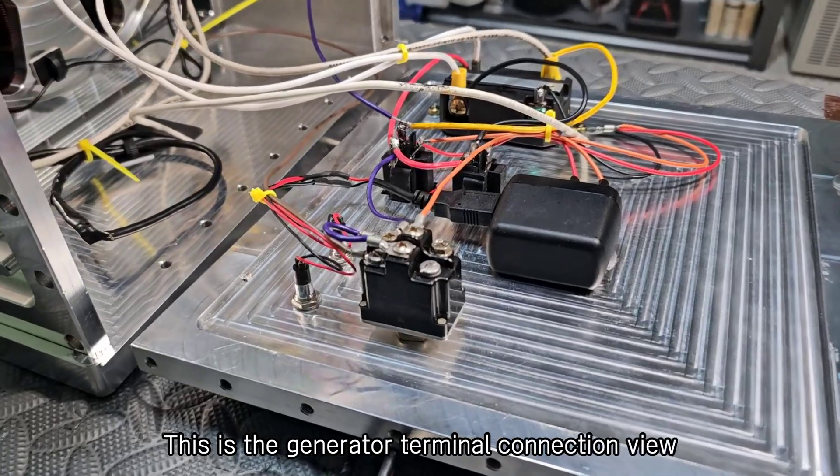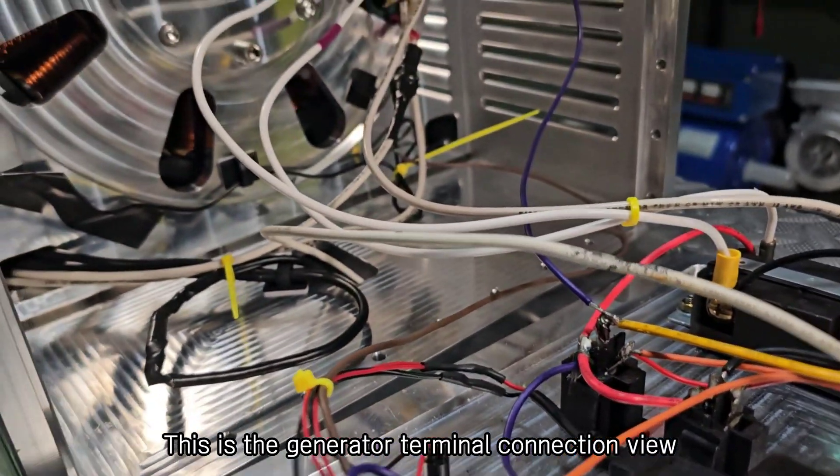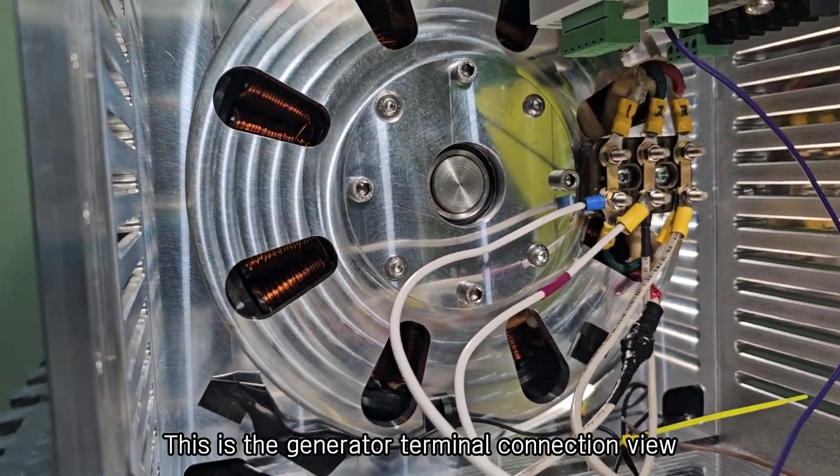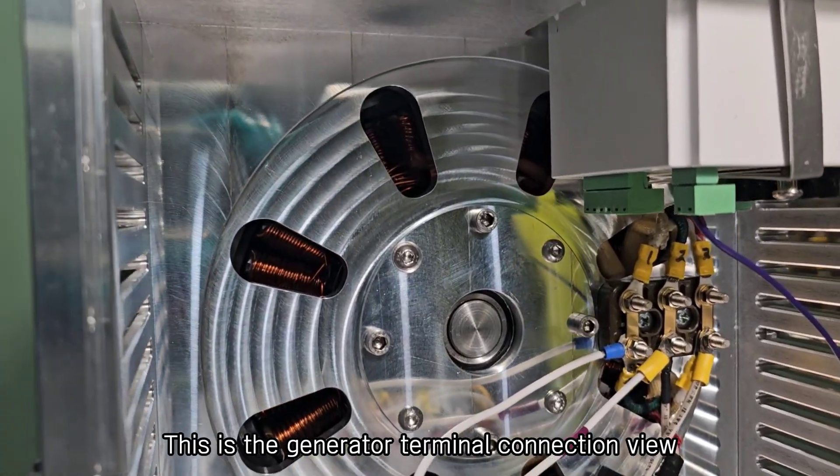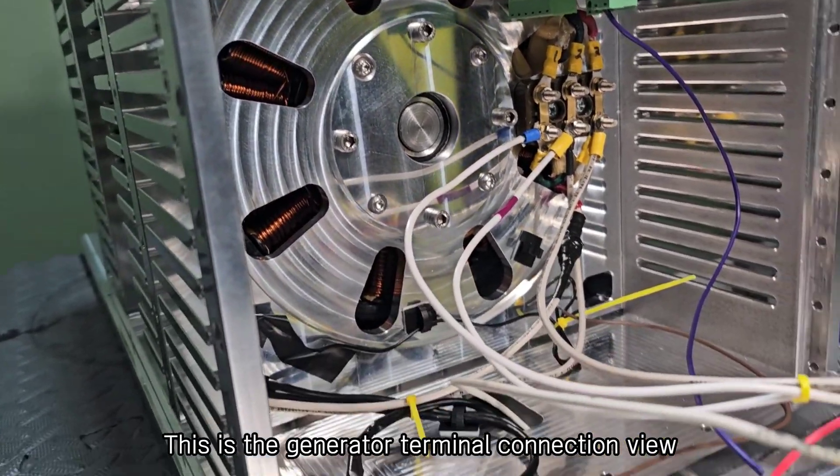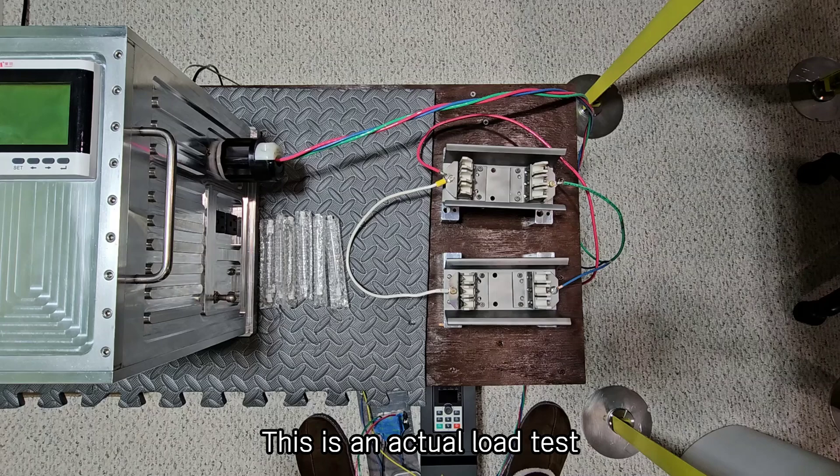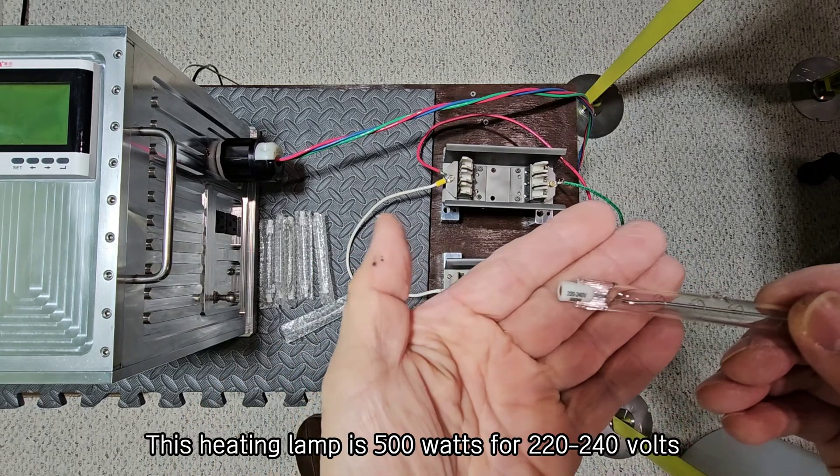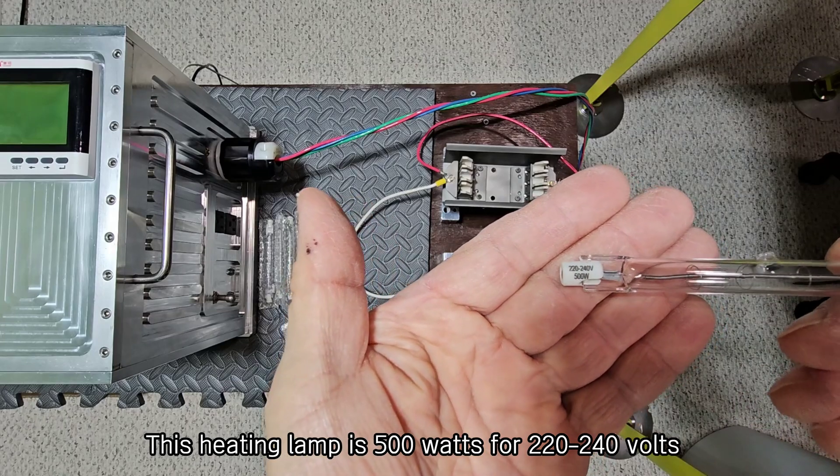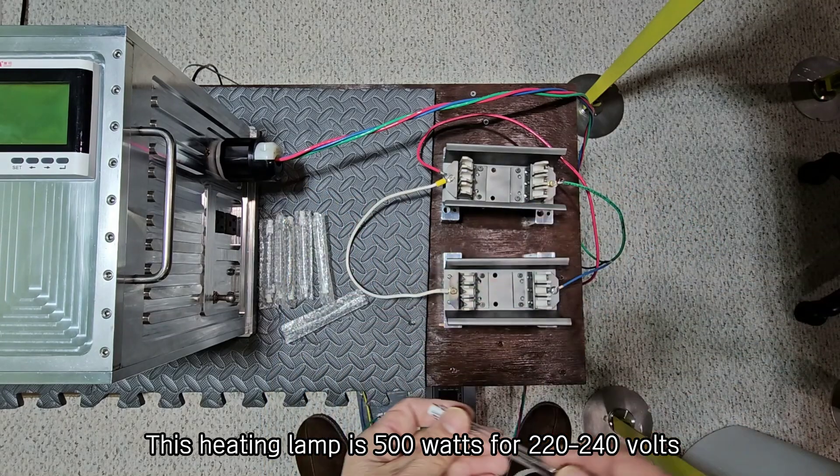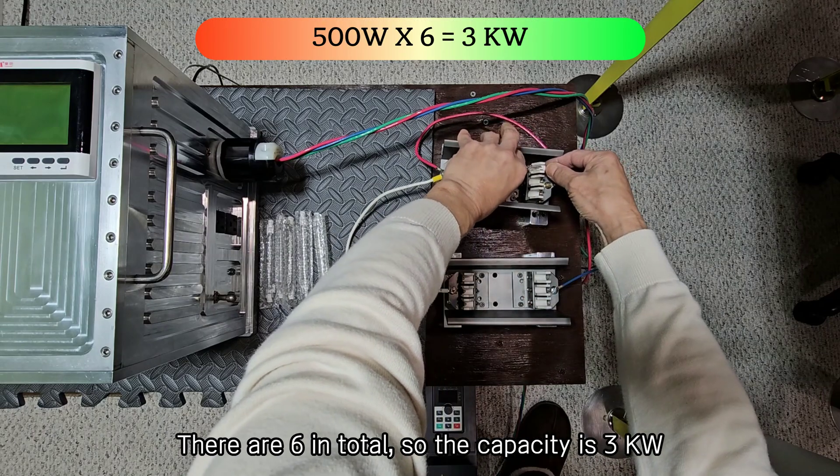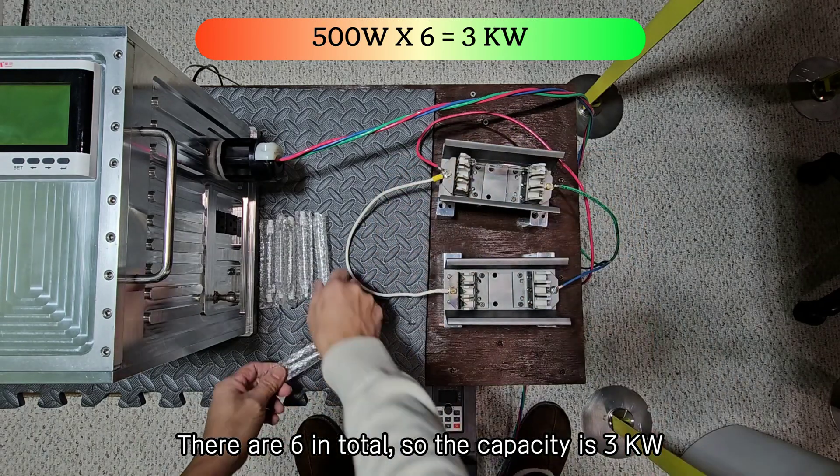This is the generator terminal connection view. This is an actual load test. This heating lamp is 500 watts for 220-240 volts. There are 6 in total, so the capacity is 3 kilowatts.